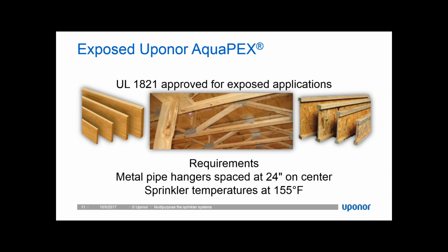So UL 1821 is the listing agency for exposed applications, specifically for thermoplastics. We can use our tubing in any type of structural configuration, so it can be dimensional lumber, or I can use it in wood I-joist applications. I can use it in floor truss applications as well. The only additional requirements that we need for this exposed application is we need to use metal pipe supports. Those are spaced every 24 inches on center, and the sprinklers that we use in this application also have to have a rating of 155 degrees or less.